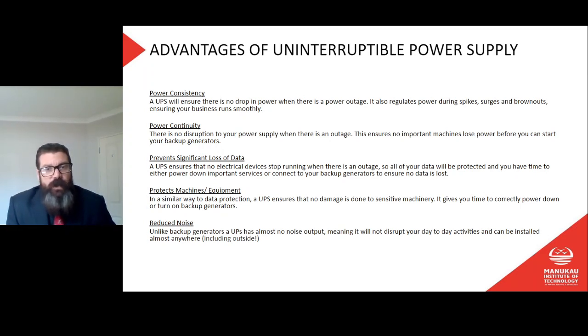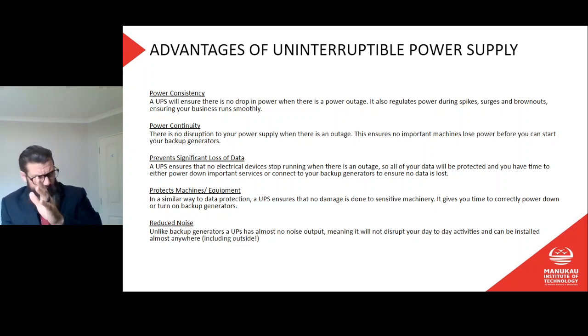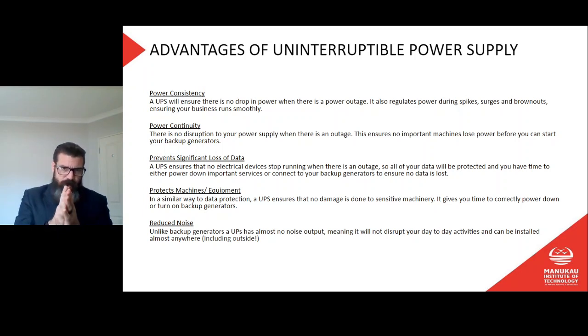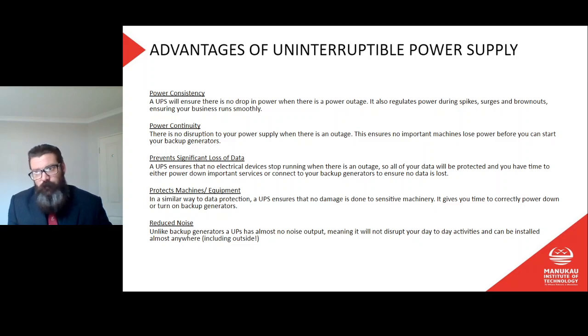Right, advantages of an uninterruptible power supply. Power consistency. A UPS will ensure there's no drop in power when there's a power outage. It also regulates power during spikes, surges and brownouts, ensuring your business runs smoothly. So that means we're not going to see, like I said, with a generator, when the power goes out, and then we turn the generator on, and then we can get power back onto our stuff, which at the very fastest, even with an automatic changeover switch and the generator starting automatically, it's going to take 5 to 10 seconds. So that 5 to 10 seconds will have no power. So our computers will switch off. Any data will be lost, or any unsaved data will be lost. So UPS can bridge that gap.